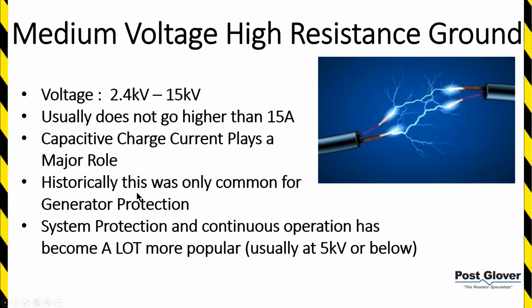Historically speaking, and I say this probably even as of 5 years ago, a lot of people would nod their head and say yes, for low voltage, use high resistance grounding, and then for medium voltage, use low resistance grounding, and that is that. And there's obviously some people who didn't do that. They did high resistance grounding at medium voltage. Usually it was for generator protection. It wasn't necessarily continuous operation. But that's kind of historically how it works.